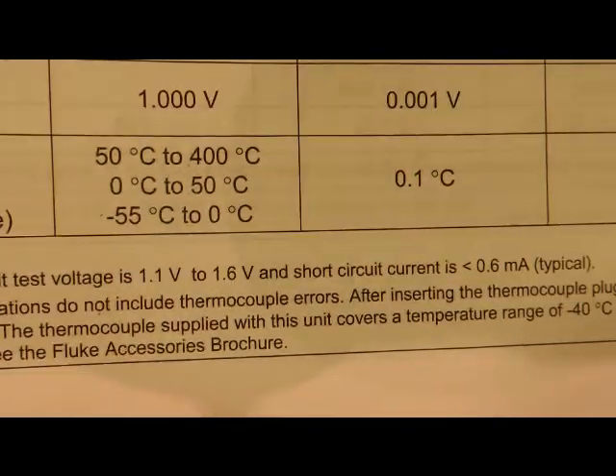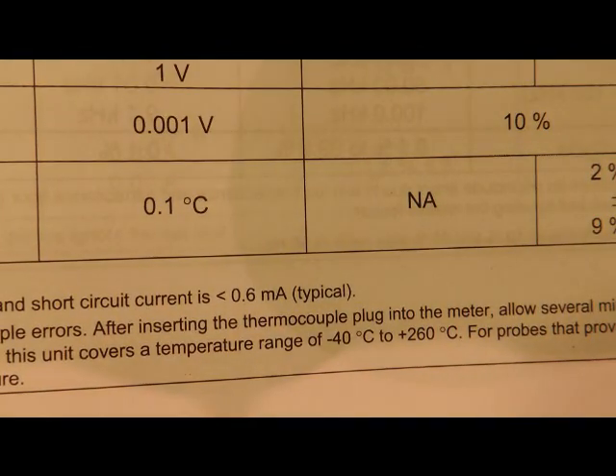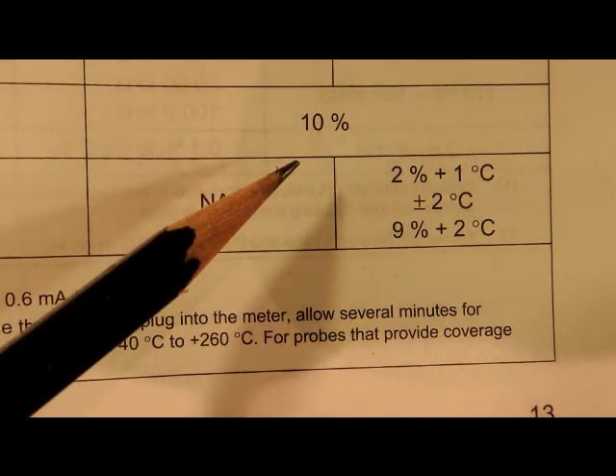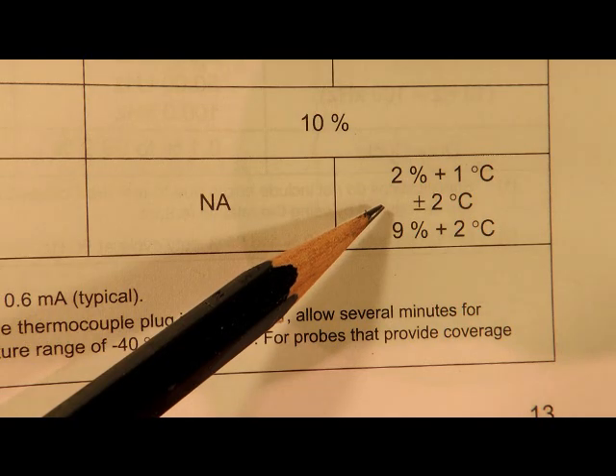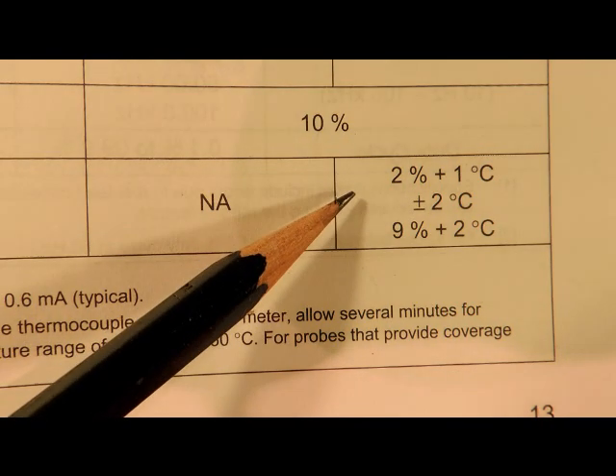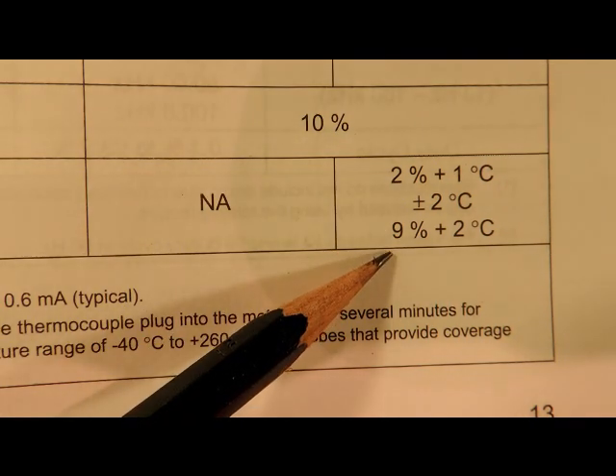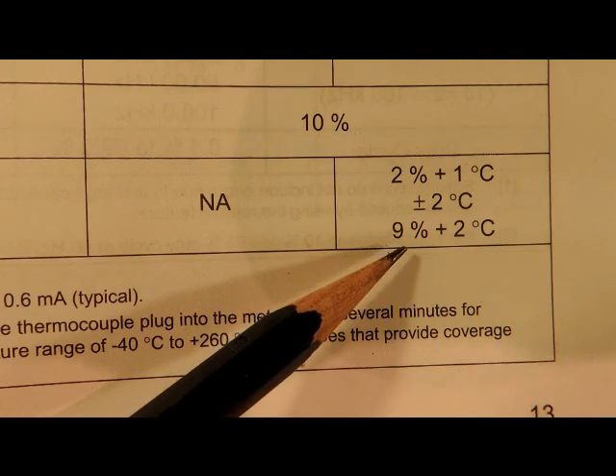The reason they have three ratings is that it has 0.1 degree resolution, but the accuracy varies. It's 2% from 50 degrees Celsius to 400 degrees, plus or minus 2 degrees Celsius from 0 to 50 degrees, which is where most people will be operating, and at very cold temperatures, minus 55 to 0, it's 9% accuracy plus or minus 2 degrees.